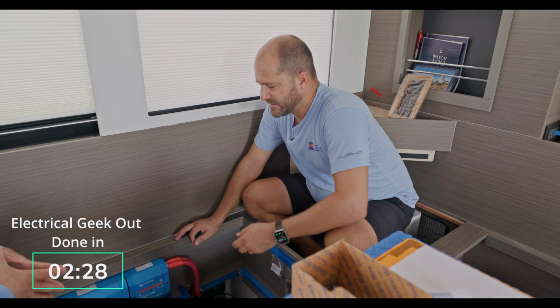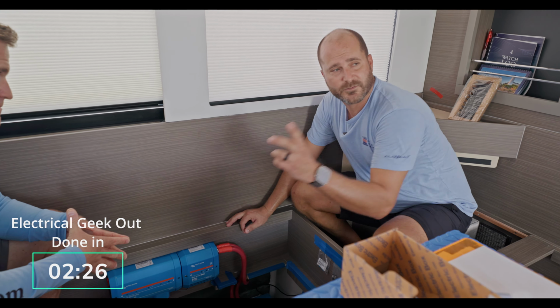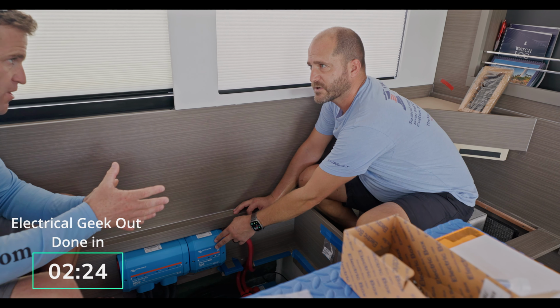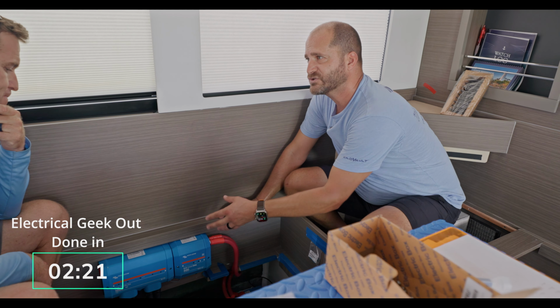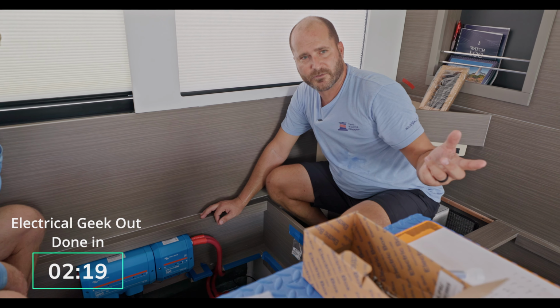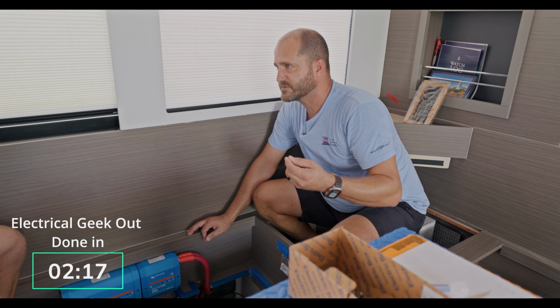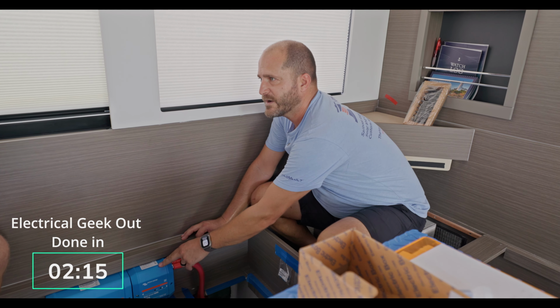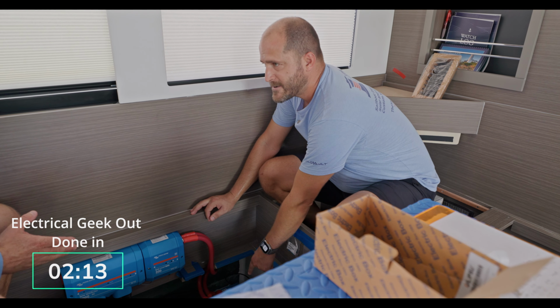So you need, as per ABYC recommendation, a switch to turn off the lithium. There is a switch in here. You can go through the servo and turn this off electronically with the contactor. But should something happen, like you lose power to the servo or a circuit breaker pops, you may not have a way of shutting this down. So it's a redundant system.